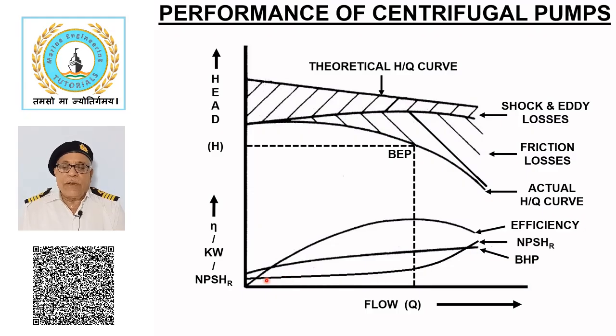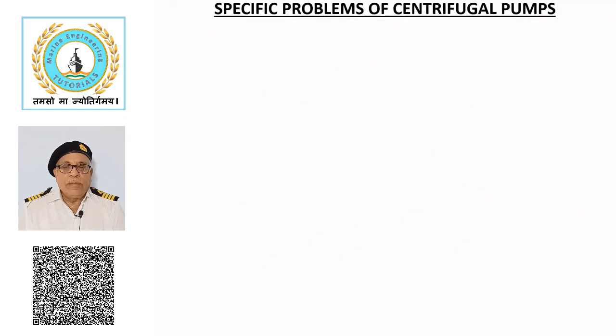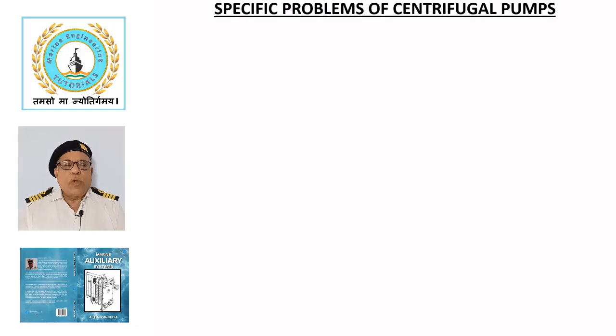Net positive suction head required up to the design point gradually increases with flow, after which the rise is very rapid. Specific problems of centrifugal pumps. The following problems are often encountered during the operation of centrifugal pumps, whose cause and remedial actions are discussed here.